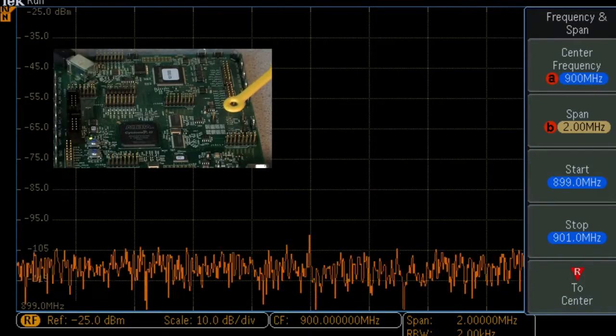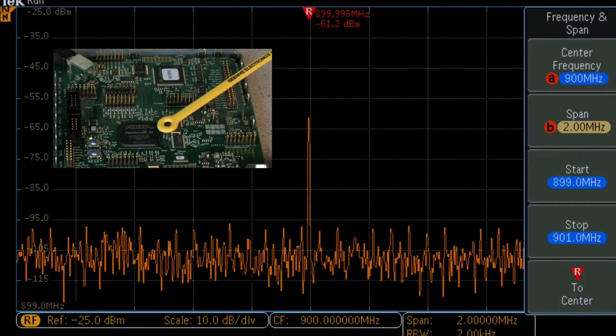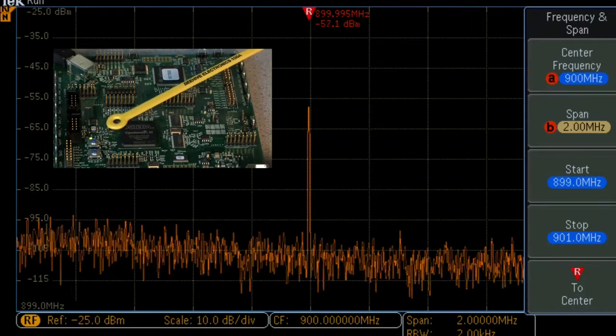Then we slowly move the loop antenna over the circuit board looking for the highest signal level at 900 megahertz.